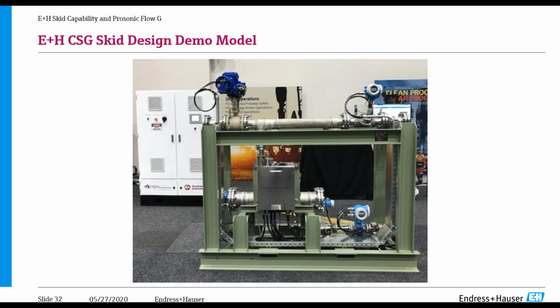Yeah, this was a photo taken from a joint presentation that we did with our alliance partner Rockwell. You can see the Rockwell control panel on the left-hand side. This system is fully integrated using standard faceplates and control blocks. It's also got the Heartbeat Technology functionality programmed into the control system, so you can automatically run a Heartbeat verification. So this is looking at the health of the instrumentation. On this skid, you can run a verification of the G300 flow meter. You can also run a verification of, in this case, a P300, which is one of our magnetic flow meters. And you can run the Heartbeat verification and check the health of the instrumentation itself.